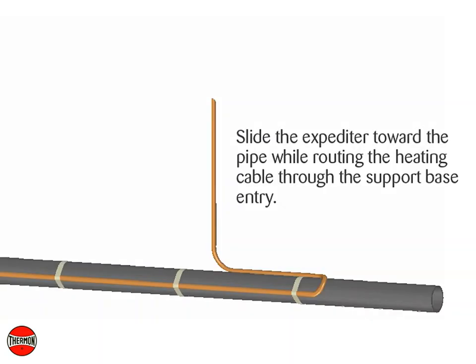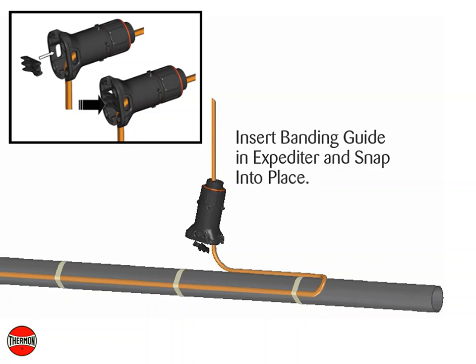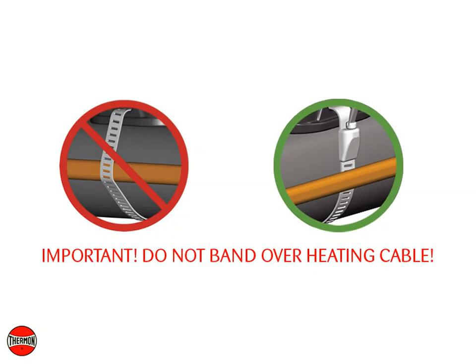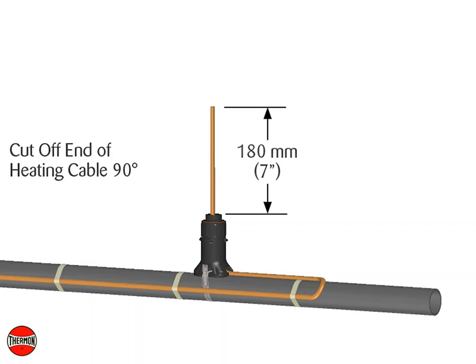Slide the expediter toward the pipe while routing the heating cable through the support base entry. Insert the banding guide in the base and snap into place. Secure the expediter to the pipe using the stainless steel pipe band. Do not band over heating cable. Cut off the end of the heating cable at a 90 degree angle, leaving a minimum of 180 millimeters or 7 inches for heating cable termination.